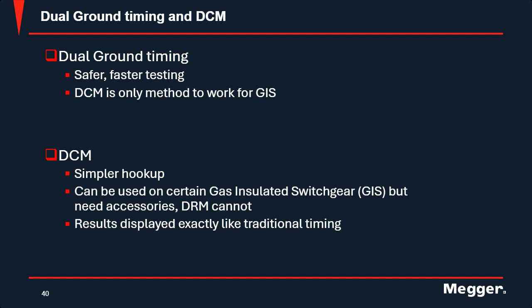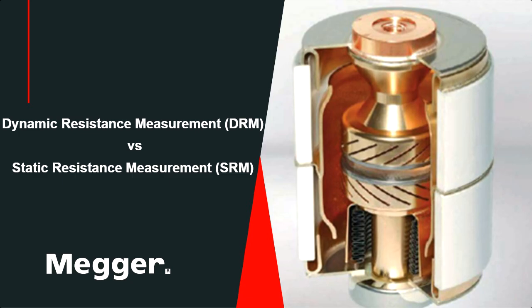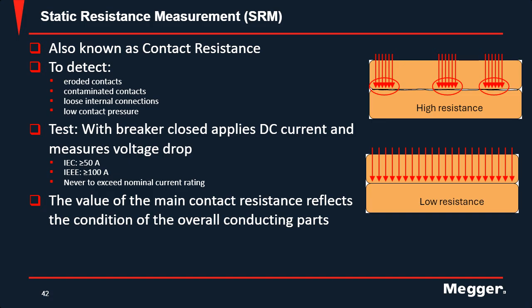So moving on to dynamic resistive measurements and static resistive measurements. We're going to start off with static resistive measurements. Most people know what this is. It's also known by another name, contact resistance. It's generally used on vacuum bottle circuit breakers, so high voltage vacuum breakers or medium voltage vacuum breakers. It detects any erosion on the contacts, any contaminants, loose internal connections, or low contact pressure. The test, with the breaker closed, applies DC current and then measures the voltage drop across that, and then using Ohm's law, it can calculate the resistance of the circuit.